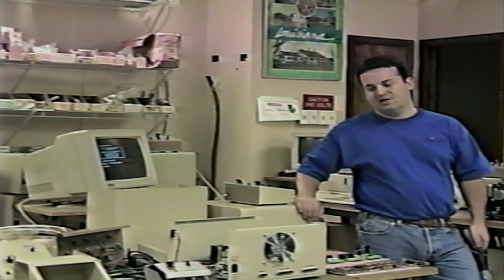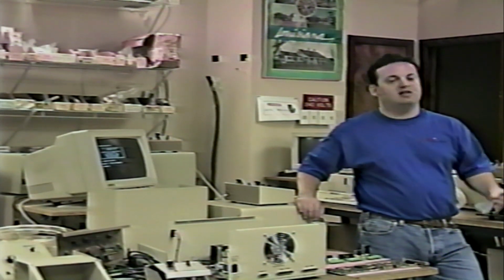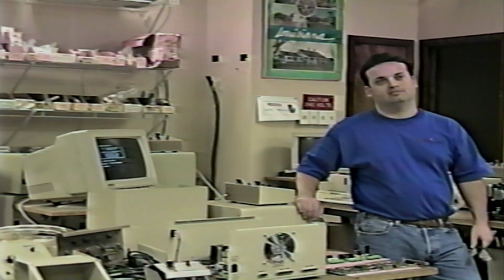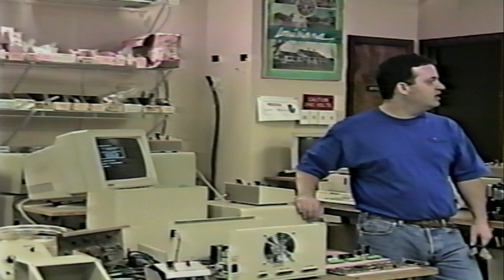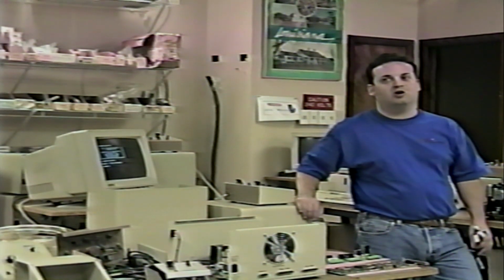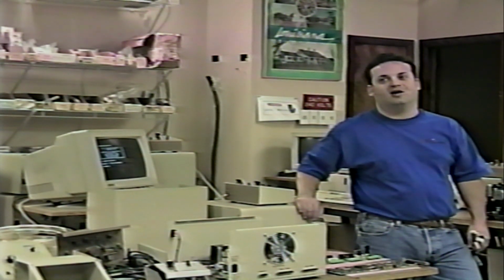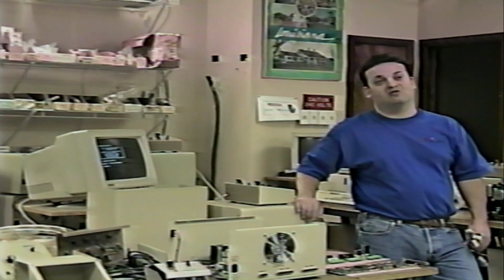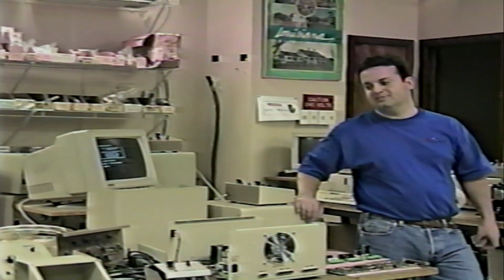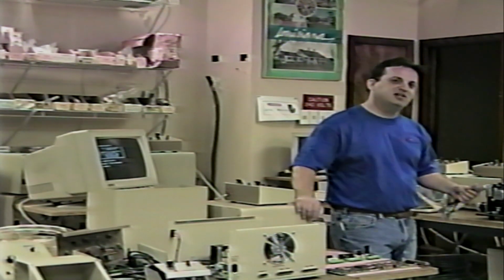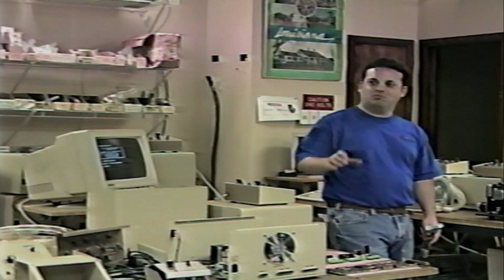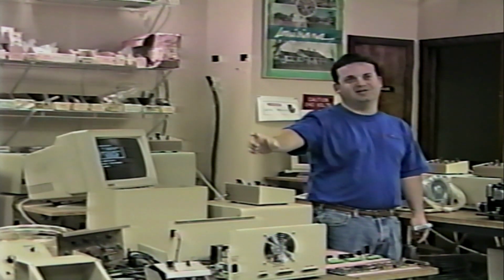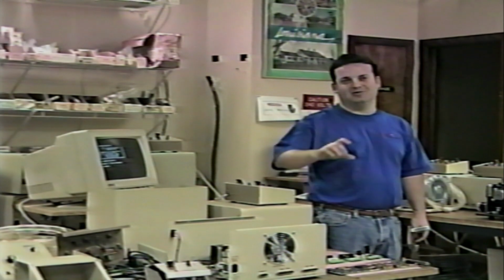Just make sure if we jumper it out at the cable that they never press mechanical home. If they do, the motors will go and grind and grind until you turn the electronics off. So if you have a customer like that, put a big black piece of tape over the mechanical home switch and tell them never to use it.